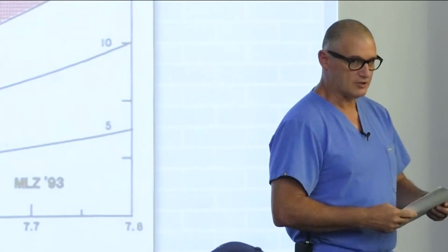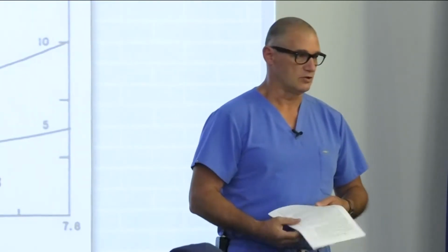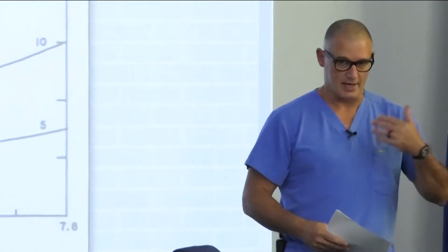So let's start at the top of the paper you've got. First, just some definitions. FiO2, we hear that term all the time. That's your fraction of inspired oxygen. So you either have a flow meter and you're bleeding O2 into your ventilator, or you have a ventilator hooked to compressed medical air and maybe even oxygen both. And then you can dial in the actual FiO2, or the oxygen percentage you want to deliver to the patient through the ventilator. Meaning every time they get a breath, they're going to get this much oxygen.